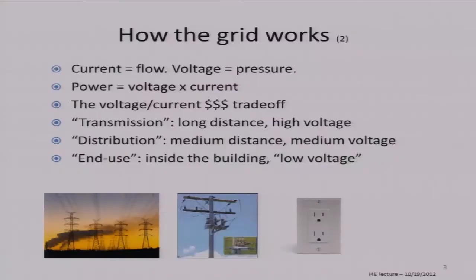So if you're going to move power long distances, you do it at more than 100,000 volts. These transmission systems here are probably 350,000 volts, somewhere in that region. That's what you use when you're going to move power more than 10 or so kilometers. To move power 100 kilometers, you use a transmission system and run it at more than 100,000 volts, which keeps the currents down to reasonable levels, hundreds of amps.